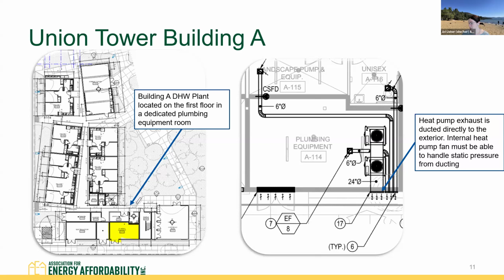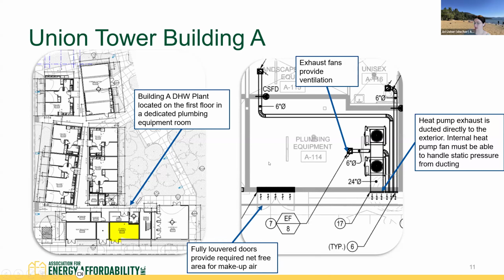Heat pump exhaust is ducted directly to the exterior of this enclosure. And we just have to make sure that the internal heat pump fans are able to handle the static pressure from the ducting. Then what we also see is there is an exhaust fan providing ventilation in this room as well. And we've also got a fully louvered set of doors to provide for makeup air to come into the room.